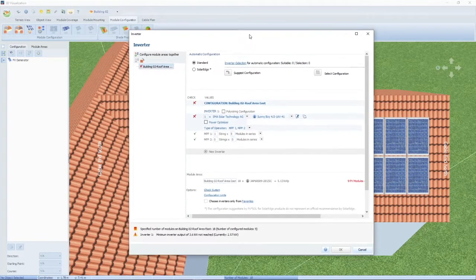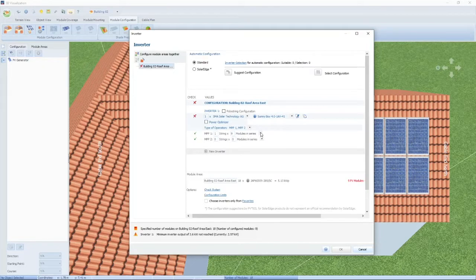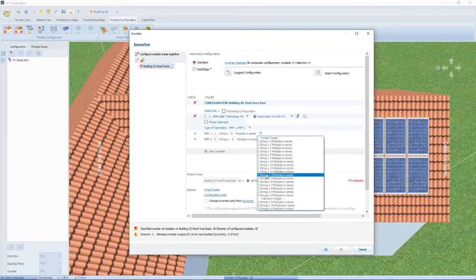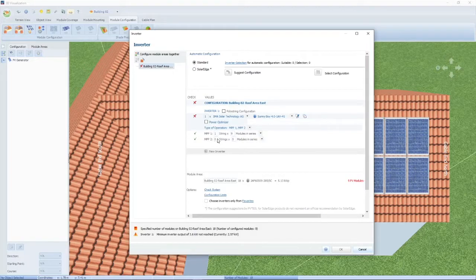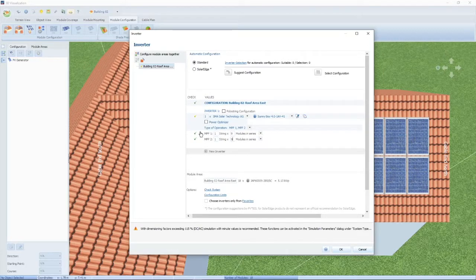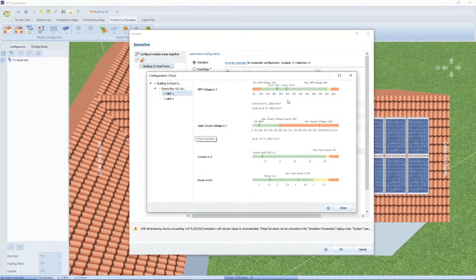We can have one string of nine modules. If you click on this button it will give you the limits — one string up to 13 modules, so we can't put all our modules in one string. We can have two strings: one string of nine on each MPPT, giving nine modules per tracker. If you click on the green arrow next to the MPP tracker, it will show you the minimum and maximum voltages — you can see it's nicely within the inverter's range. The open-circuit voltage is lower than the maximum voltage of 600 volts.